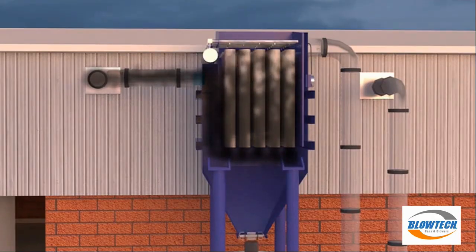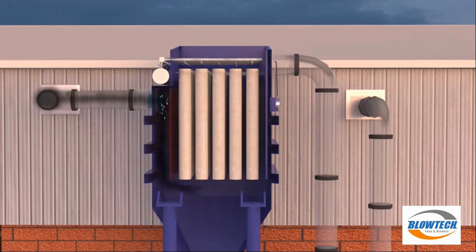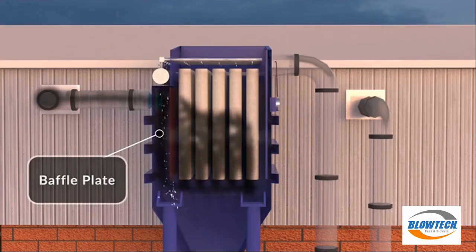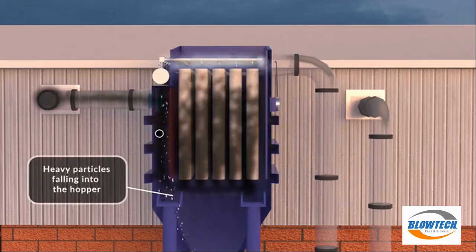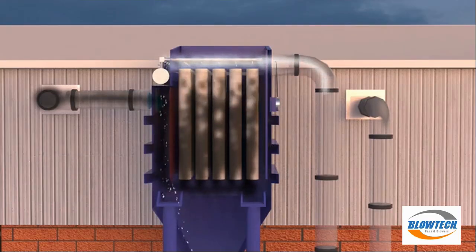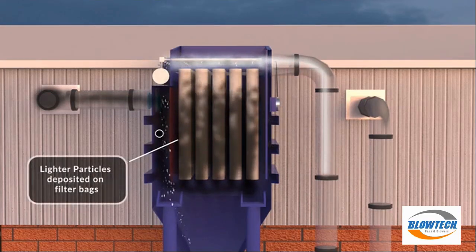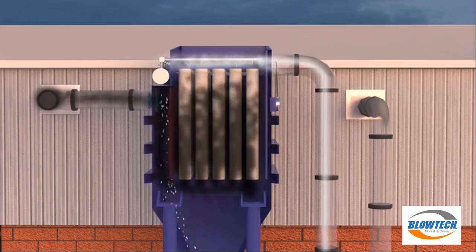The air passes through the filter bags. Due to the use of a baffle plate, the heavy particles fall down into the hopper, and the lighter dust particles get deposited on the exterior surface of the bags.